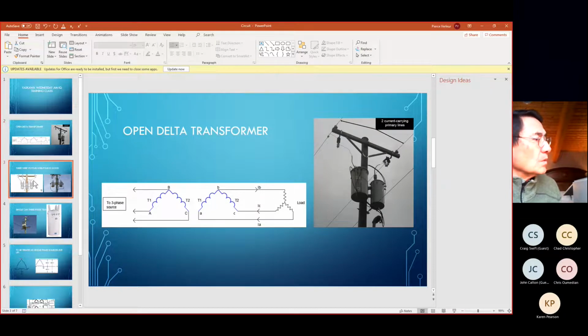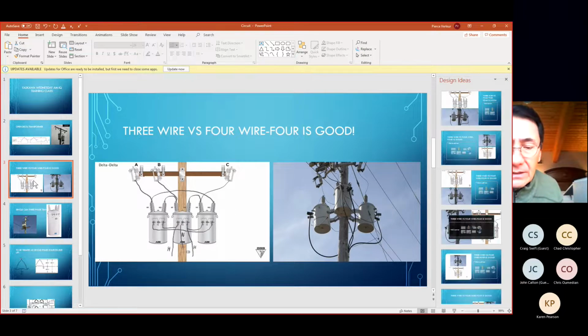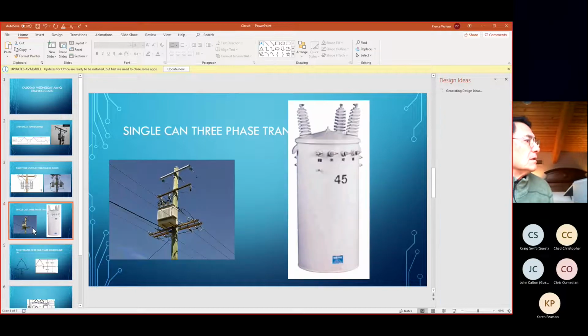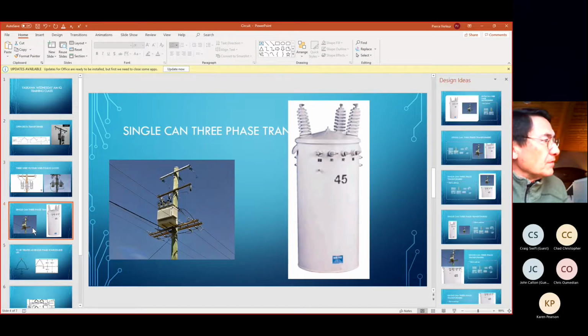So that's another warning. If you don't see 4 lines coming down the pole, you need to call your Yaskawa person, and we need to discuss the application with you to make sure that you're safe. These are single can 3-phase, but again, you can count the 4 lines. Here we have 4 conductors, the 3 phases and neutral. So a single can versus 3 can configuration can still be a balanced, grounded supply coming off the pole.